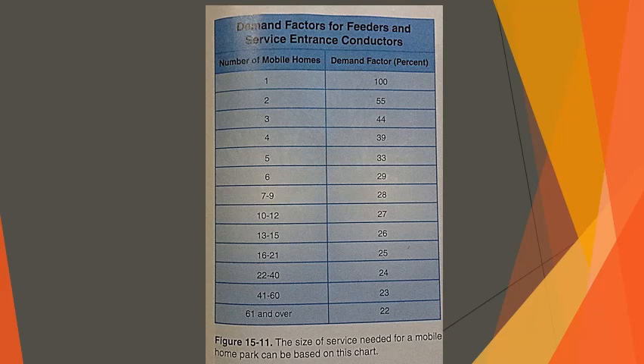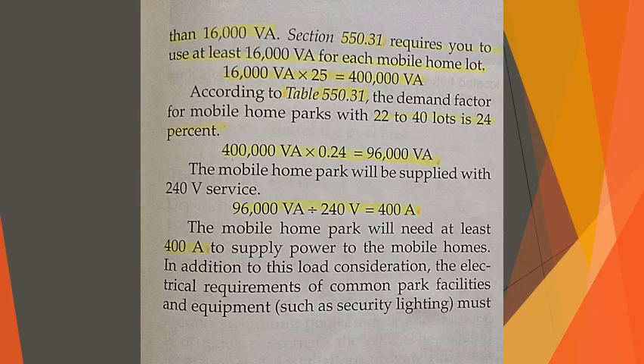The mobile home park will be supplied with a 240 volt service. So 96,000 VA divided by 240 volts equals 400 amps. The mobile home park will need at least 400 amps to supply power to the mobile homes. In addition to this load consideration, the electrical requirements of common park facilities and equipment, such as security lighting, must be added onto the overall total service demand. Refer also to NEC Article 550.30. That is the example that we just discussed.